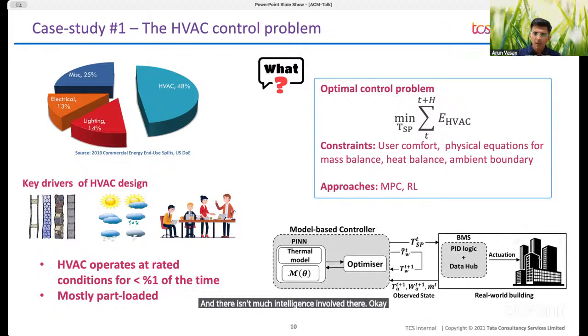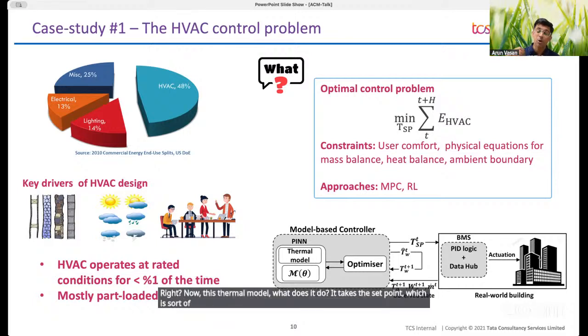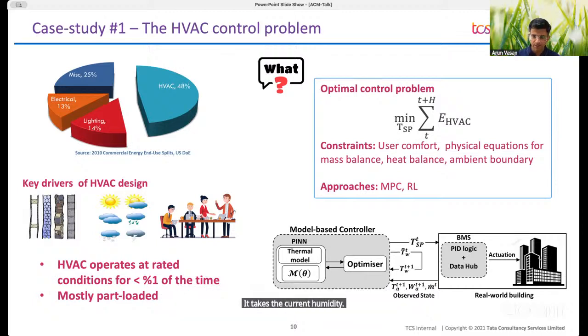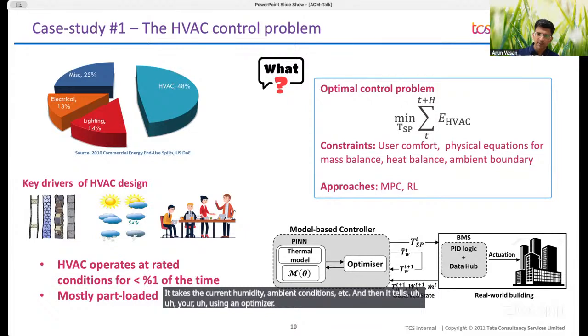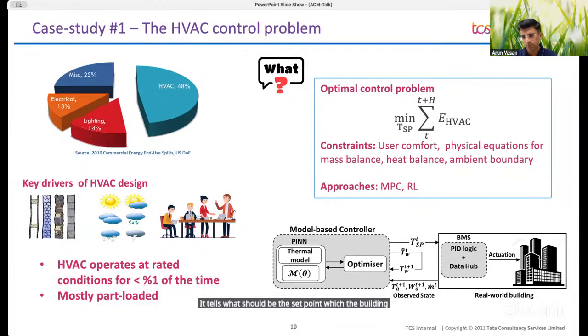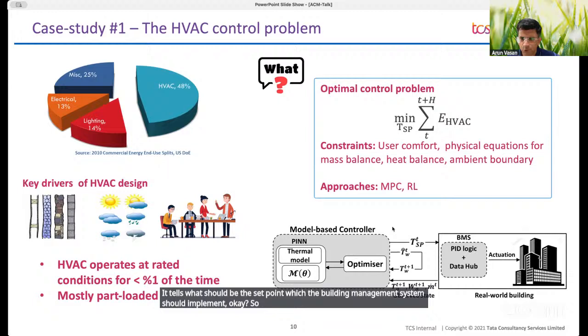Now for us to decide what is an optimal set point, I need a thermal model of the building. This thermal model takes the current humidity, ambient conditions, etc., and then, using an optimizer, it tells what should be the set point which the building management system should implement. So this is roughly the flow of the thing.